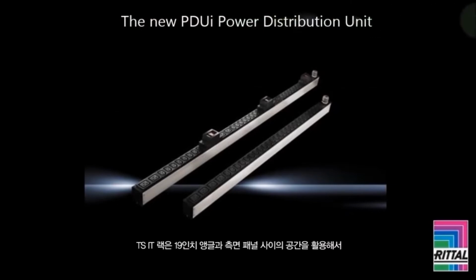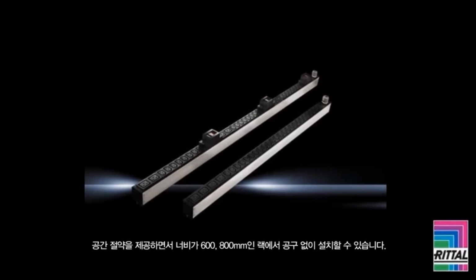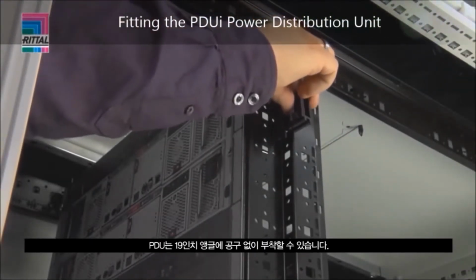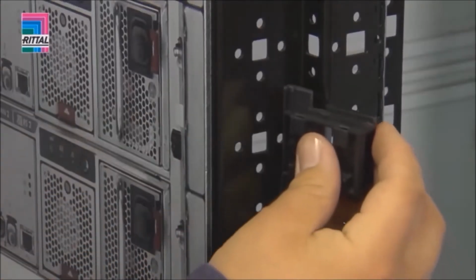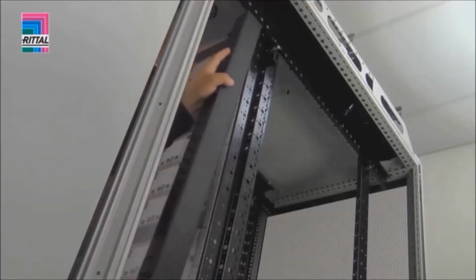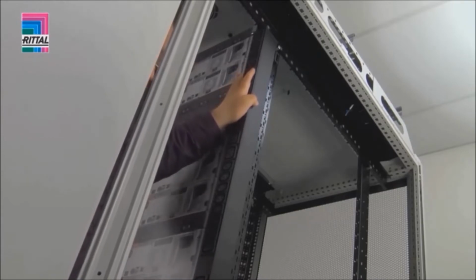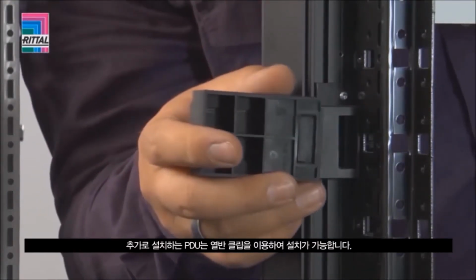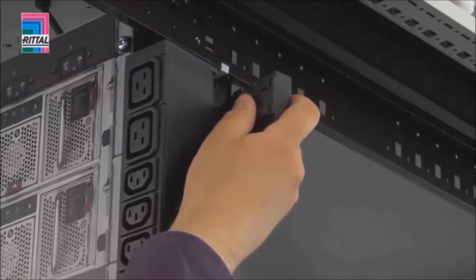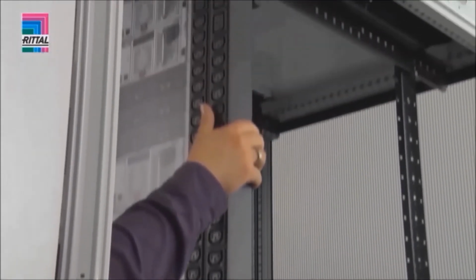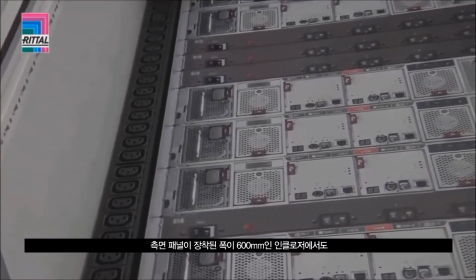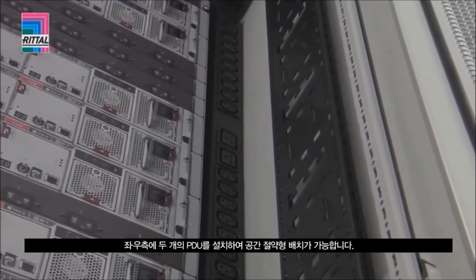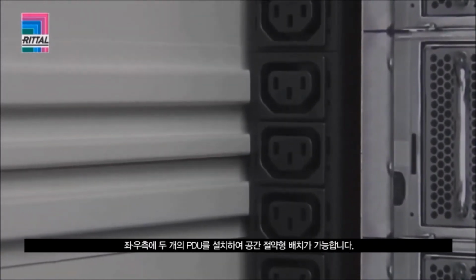The TS IT rack accommodates the new PDUi in the 0U space between the 19-inch level and the side panel, offering space-saving, tool-free assembly for 600 and 900 mm rack width. The new busbar is installed in the rear 19-inch level without using tools. Baying the second bar is equally straightforward, with the help of a baying clip. The space-saving positioning of two busbars on the left and right is also possible in the 600 mm wide enclosure, even with a fitted side panel.